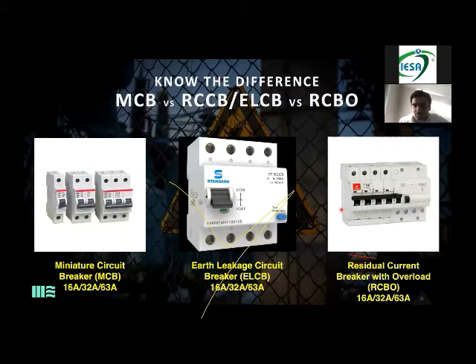Again, very important, safety. These are all safety equipment which are available. So what is the difference between an MCB, an RCCB, or an ELCB, versus an RCBO? We've spoken about those 5 points which can go wrong. The first point was undersized wiring. The second was overload. The MCB is saving you from 2 functions.